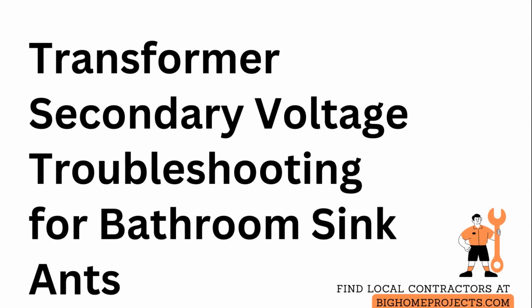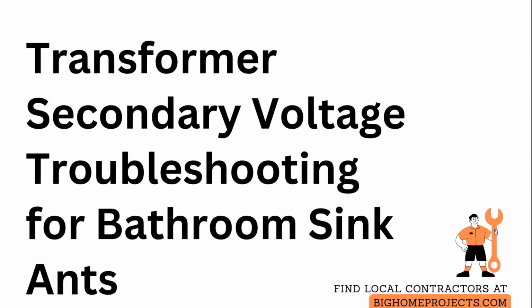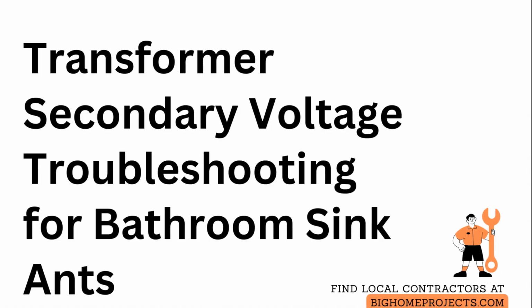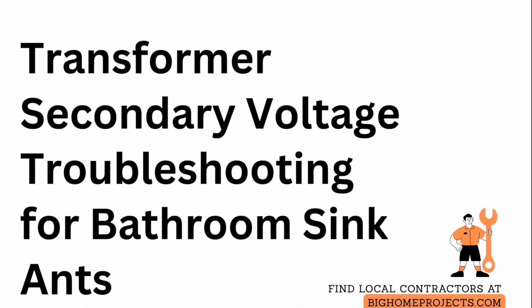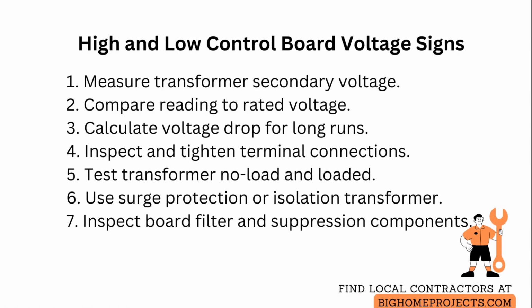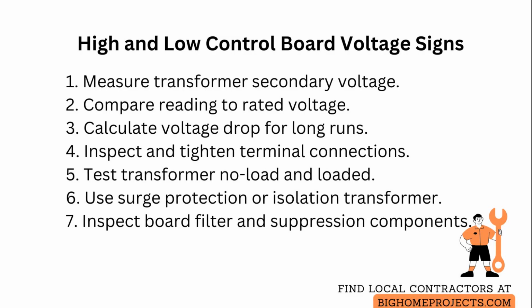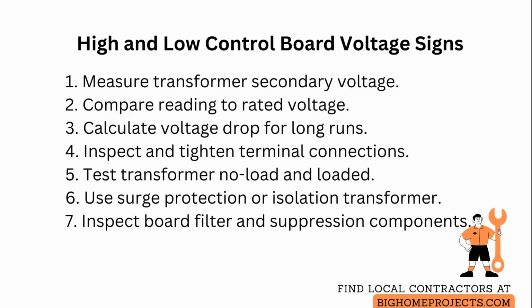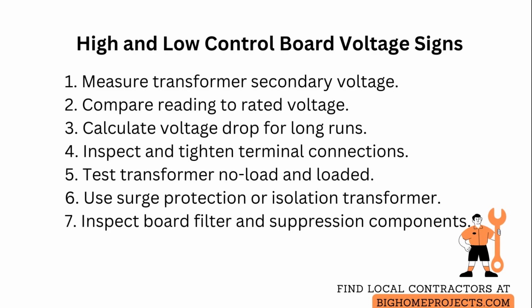High or low voltage at a control board's terminals can indicate underlying failures that demand immediate diagnostic steps. Measure voltage at the transformer secondary with a quality digital multimeter set to the appropriate alternating current range and compare readings to the manufacturer's rated secondary voltage written on the transformer label.